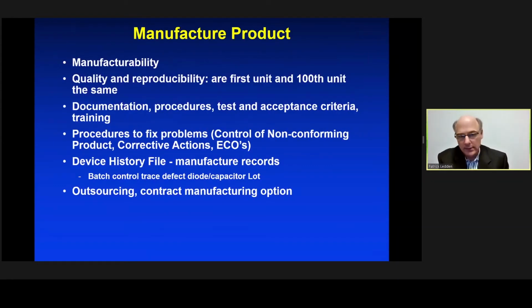Once you have your newly approved medical device, your new MRI coil, well, you've got to make it. And here is where manufacturability really comes into play. In particular, you need to have quality and reproducibility. Is the first unit and the 100th unit going to be the same? In the end, all your documentation, your procedures, your test acceptance criteria, and your training are tested by this. Do they actually lead to building a quality product? Sometimes things don't go right, and you need to have procedures to fix problems, which is part of your quality management system, such as control of non-conforming product, corrective actions, engineering change orders.